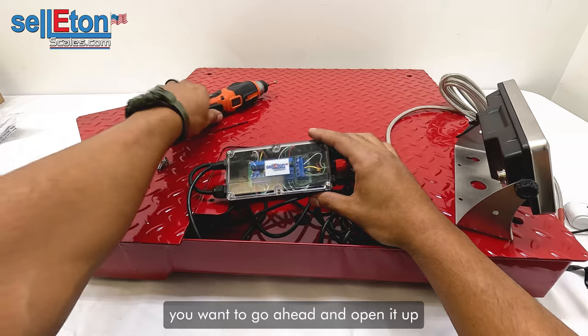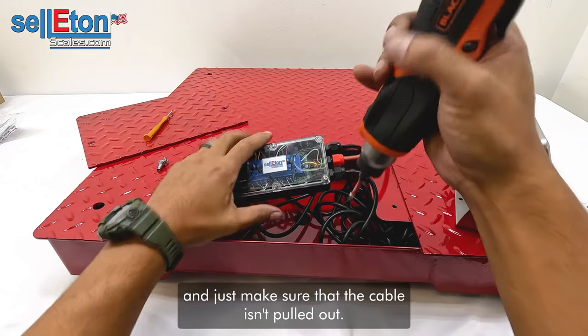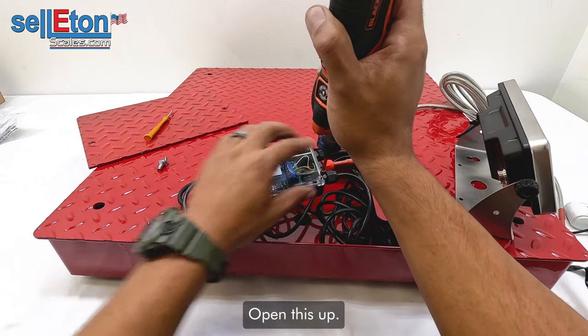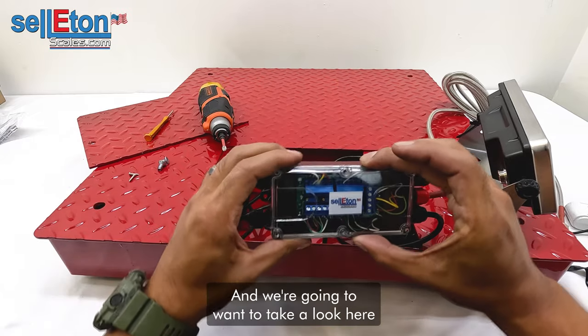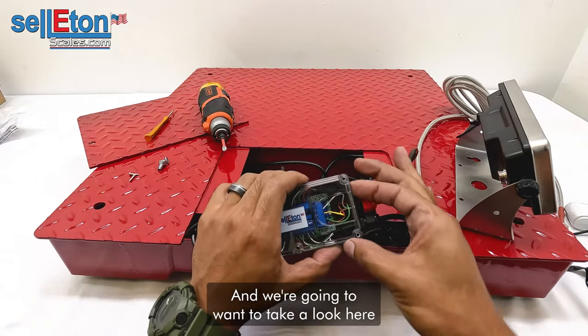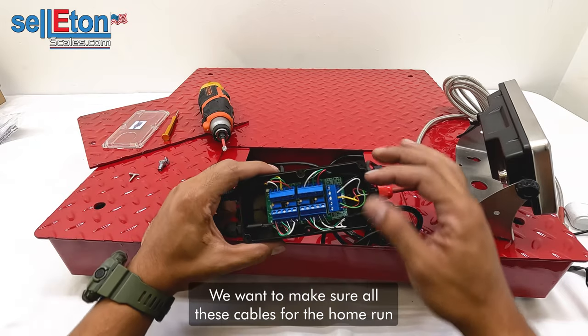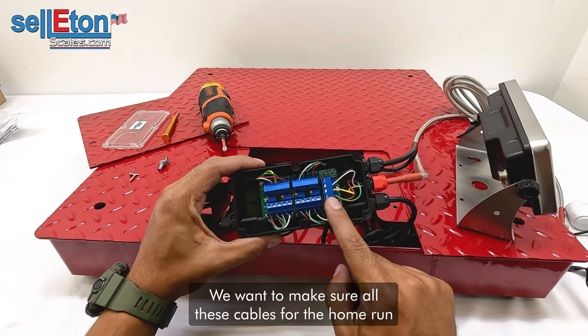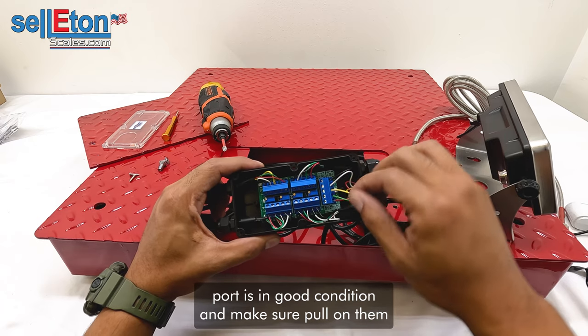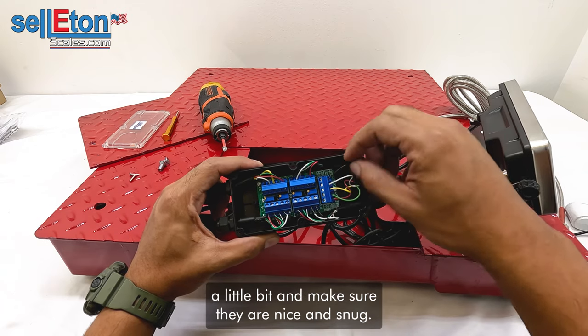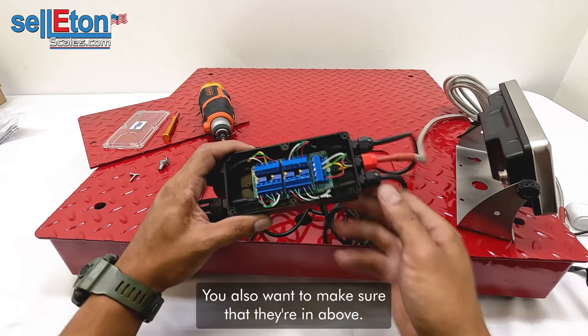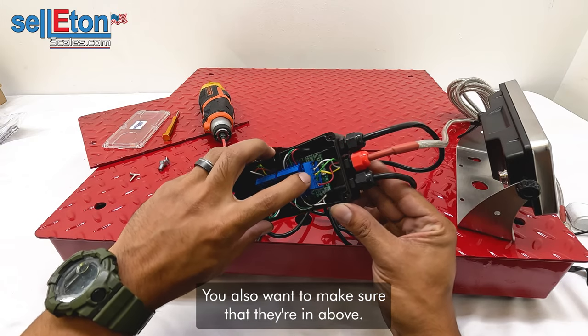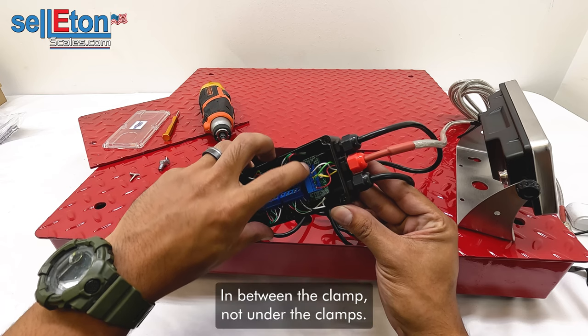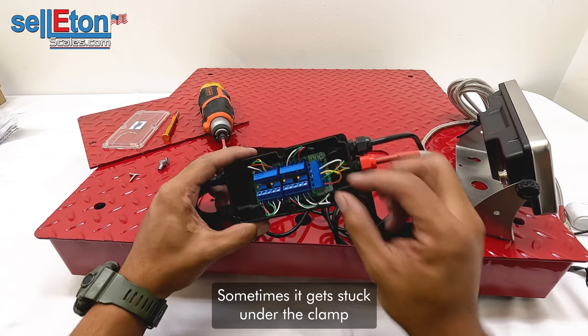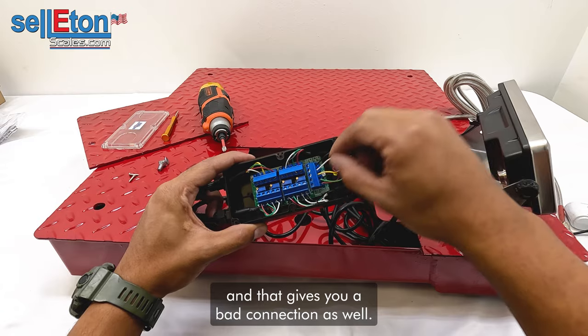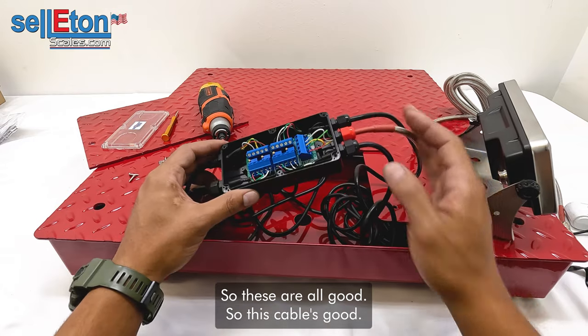For the junction box, you want to go ahead and open it up and just make sure that the cable isn't pulled out. Open this up. We're going to want to take a look inside the junction box. We want to make sure all these cables for the home run port are in good condition. Pull on them a little bit and make sure they're nice and snug. You also want to make sure that they're in between the clamp, not under the clamp. Sometimes it gets stuck under the clamp, and that gives you a bad connection as well. So these are all good. So this cable is good.